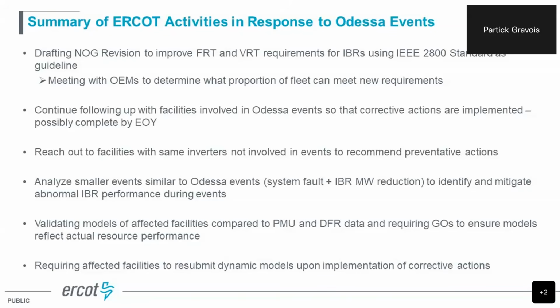We are in the process of drafting new nodal operating guides for our voltage and frequency ride-through requirements for inverter-based resources, and we're basing those off the IEEE 2800 standard that just came out. We are meeting with several OEMs of both wind and solar to determine what proportion of the current fleet can meet these new requirements. We've had a couple already. We've got another 5 or 6 that we're going to meet with to see what can meet these newer requirements and what we need to adjust a little bit.